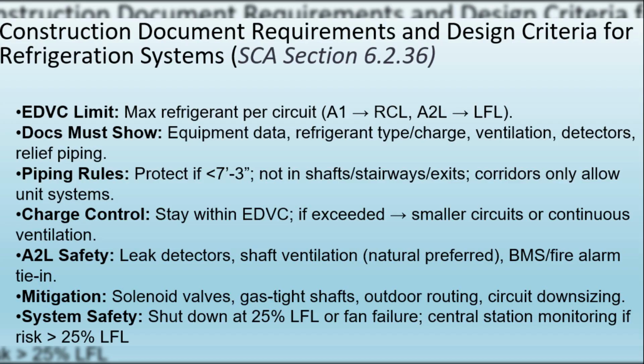Construction documents must clearly show critical details: equipment location and size, refrigerant type and quantity, ventilation methods, detector and emergency switch locations, pressure relief piping, and safety group classification. Designers also need to include refrigerant concentration limit calculations and piping routes. Refrigerant piping rules are strict. Piping below 7 feet 3 inches must be concealed or protected. It cannot run through shafts, stairways, elevators, or exits. In corridors and lobbies, only factory-assembled unit systems are allowed. Split systems or VRF piping are prohibited.